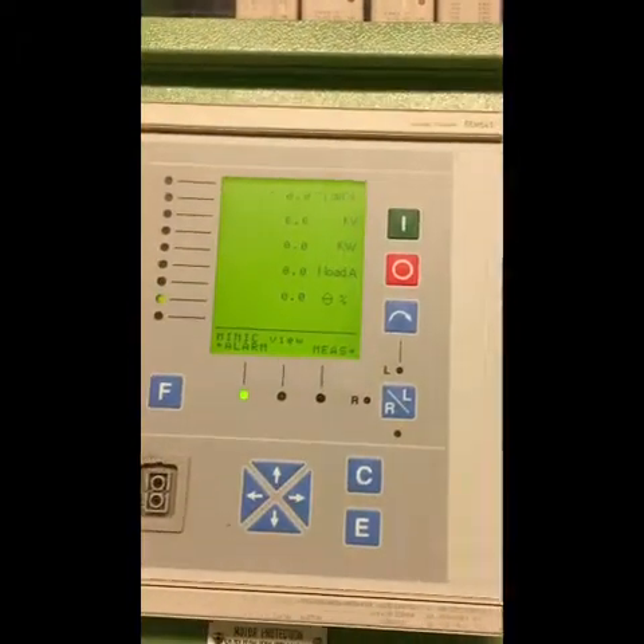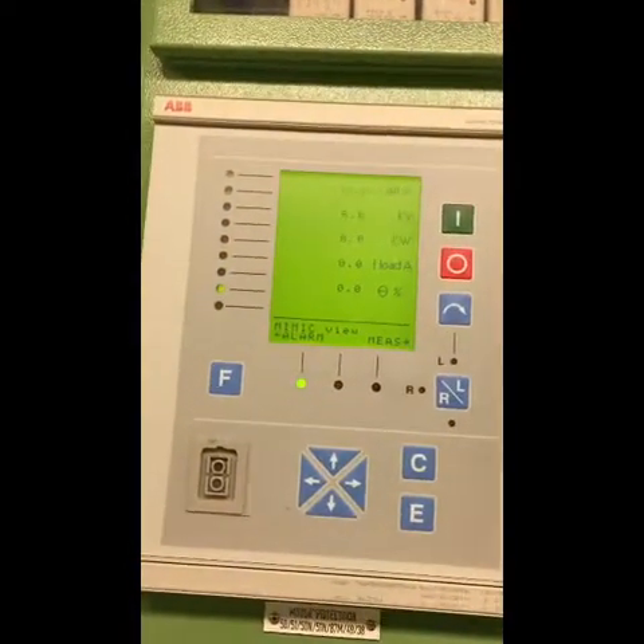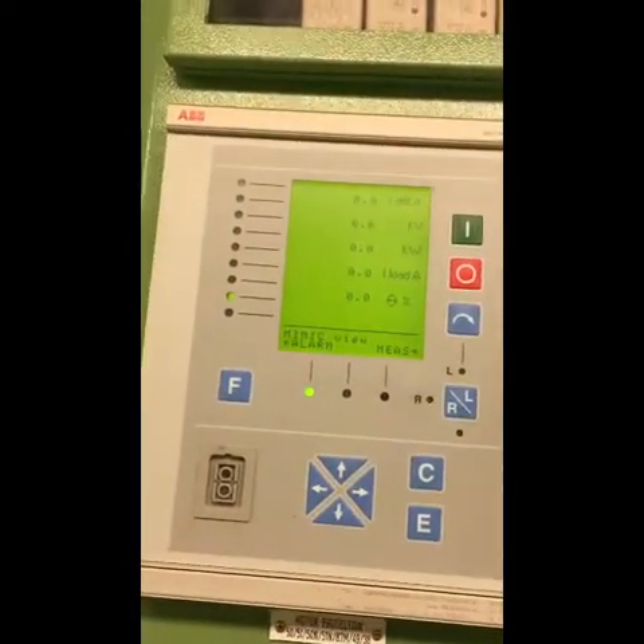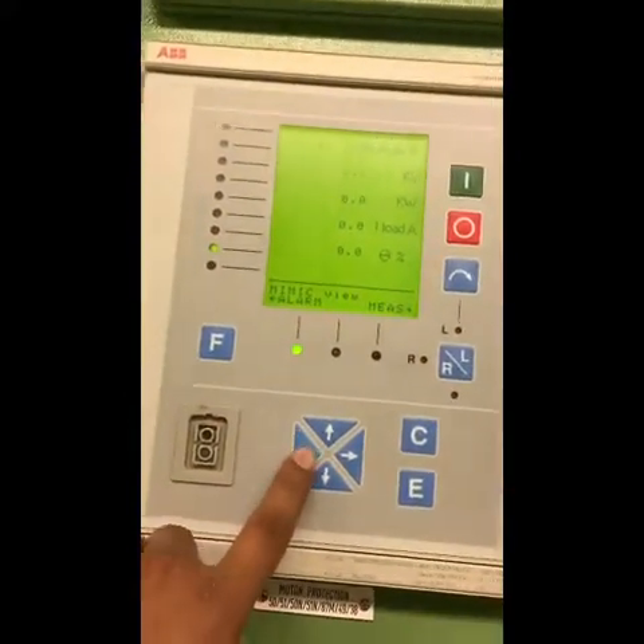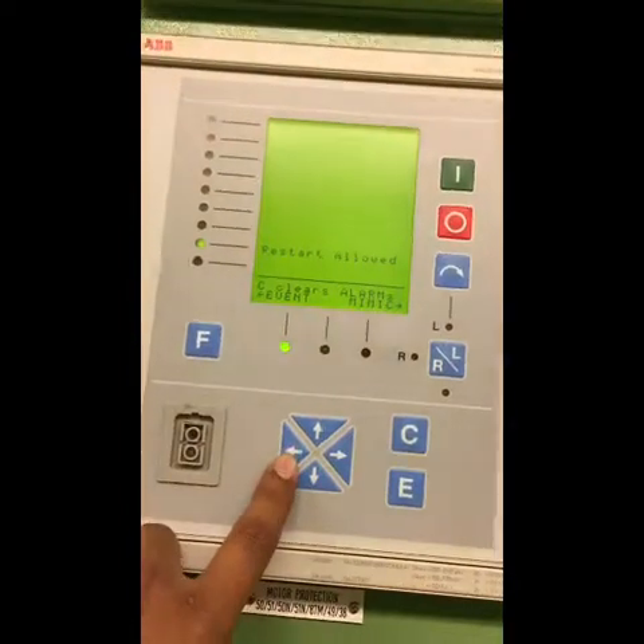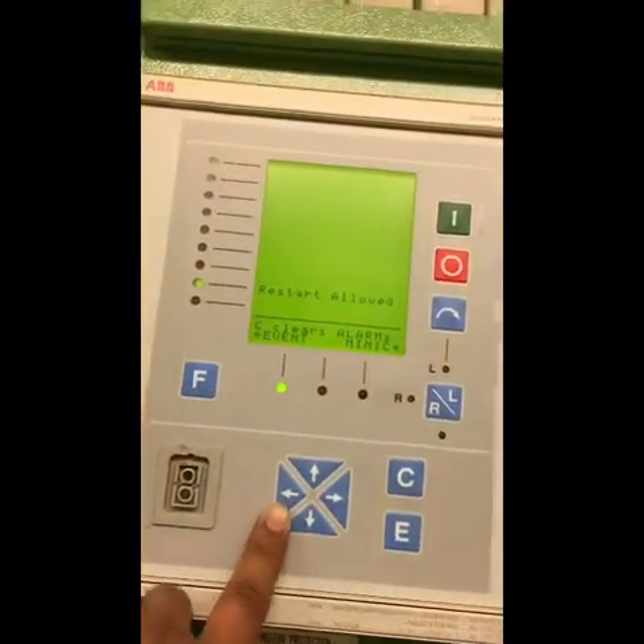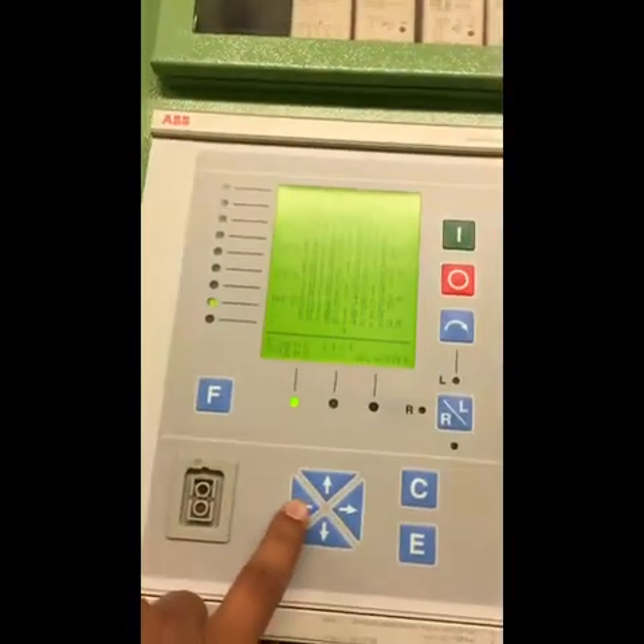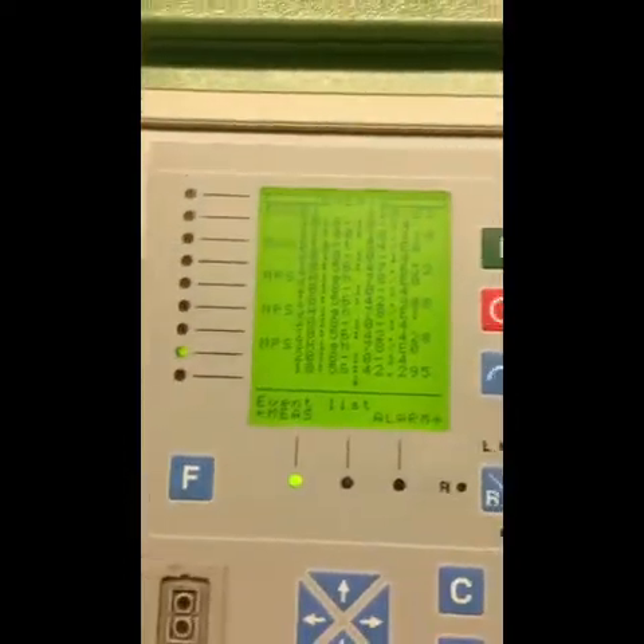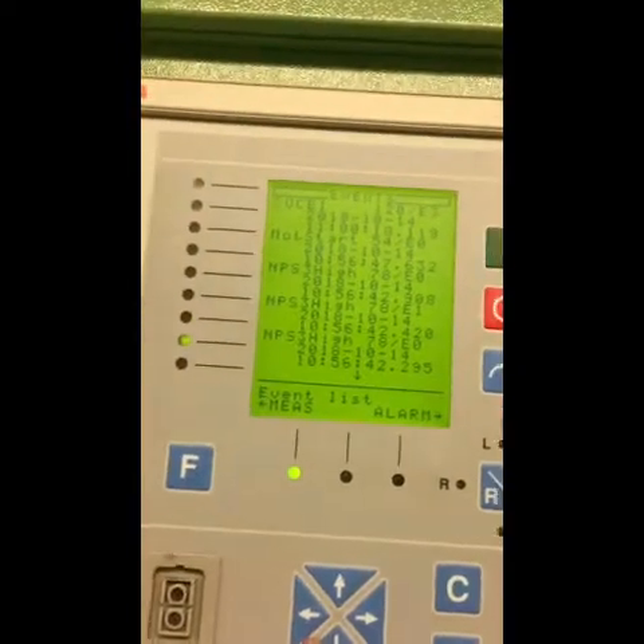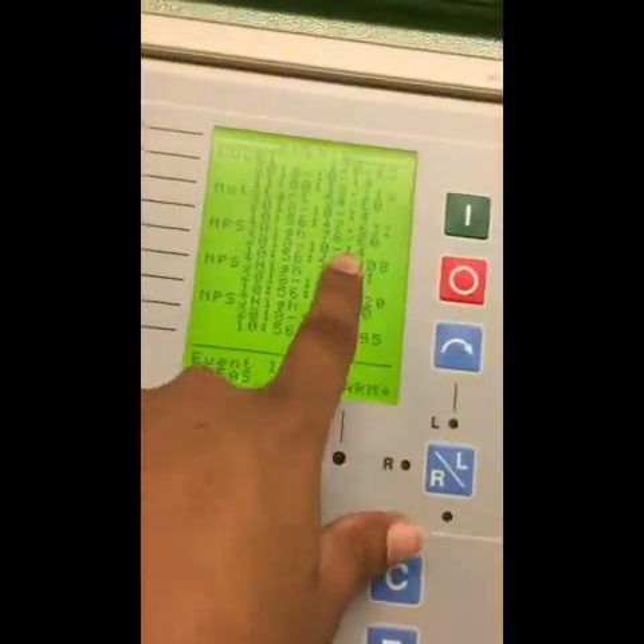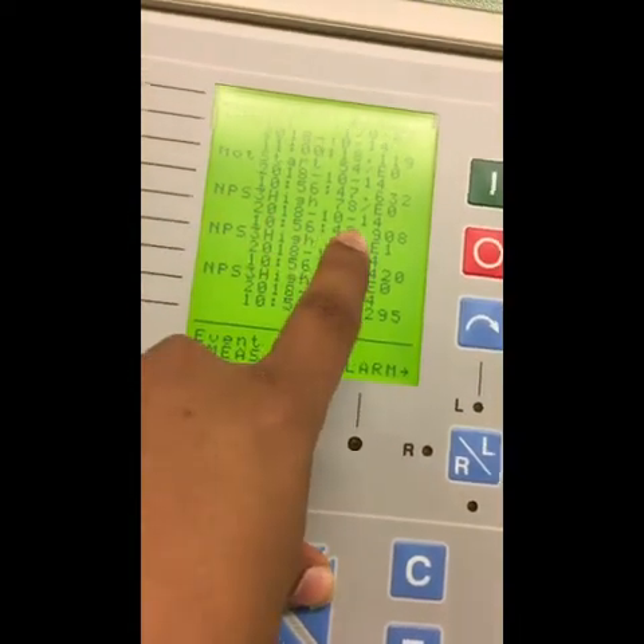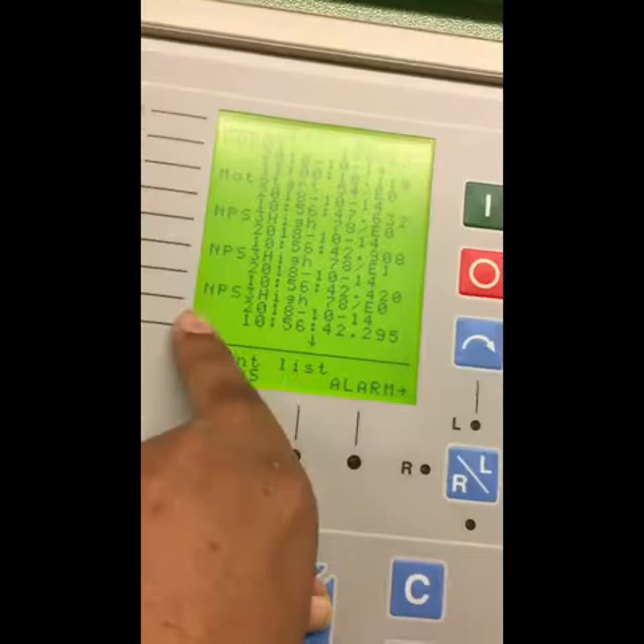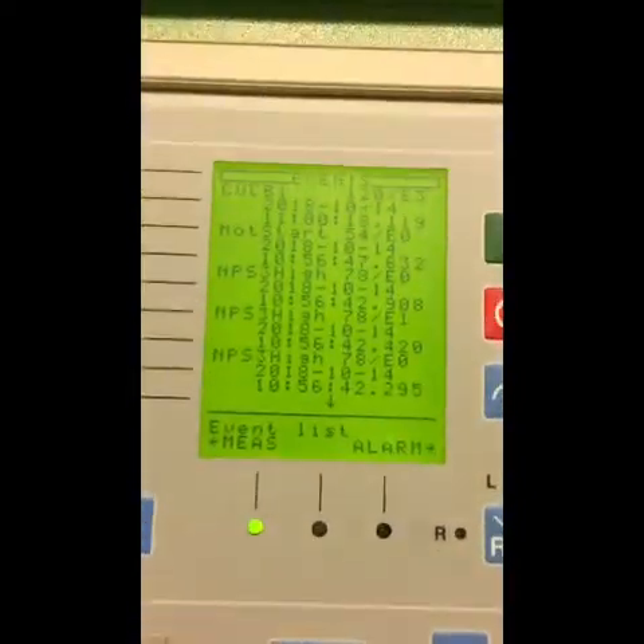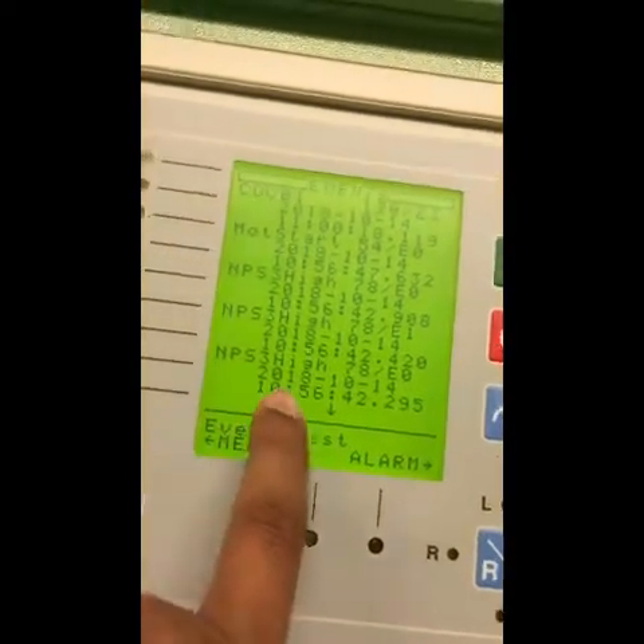For REM 543, I can read the fault record by pressing on the left arrow. This is the alarm existence. There is no alarm. Restart is allowed. I can start this pump again, and then I press left again, and I see all the events of what happened to this protection relay. The motor started at this date, negative phase sequence tripped at this date. All the faults will be showing here, including the date and the time.